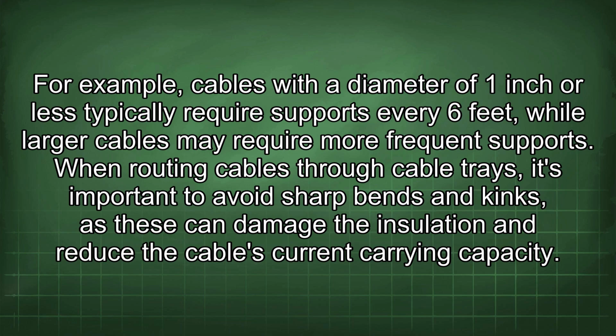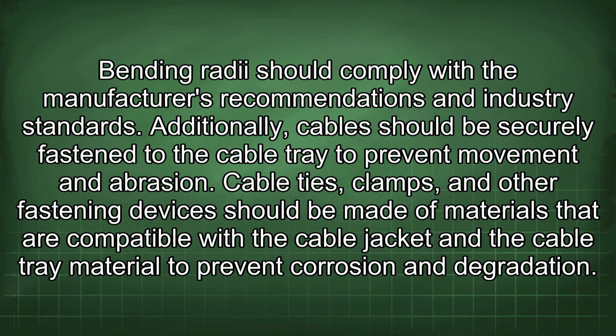When routing cables through cable trays, it's important to avoid sharp bends and kinks, as these can damage the insulation and reduce the cable's current carrying capacity. Bending radii should comply with the manufacturer's recommendations and industry standards. Additionally, cables should be securely fastened to the cable tray to prevent movement and abrasion. Cable ties, clamps, and other fastening devices should be made of materials that are compatible with the cable jacket and the cable tray material to prevent corrosion and degradation.